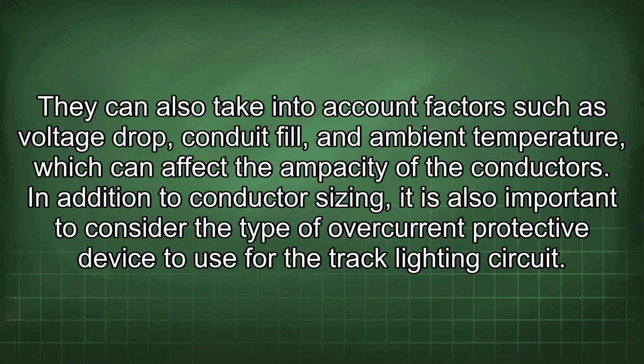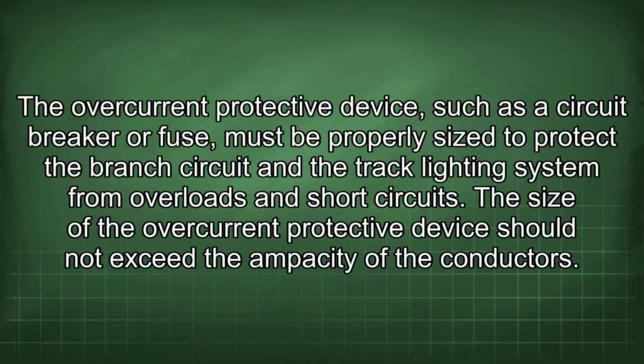They can also take into account factors such as voltage drop, conduit fill, and ambient temperature, which can affect the ampacity of the conductors. In addition to conductor sizing, it is also important to consider the type of overcurrent protective device to use for the track lighting circuit. The overcurrent protective device, such as a circuit breaker or fuse, must be properly sized to protect the branch circuit and the track lighting system from overloads and short circuits.